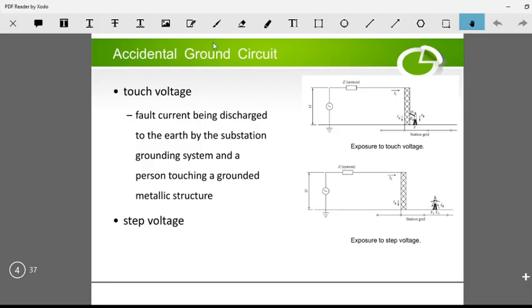So you have the touch voltage and the step voltage. Let's talk about touch voltage first. Touch voltage is defined using the fault current being discharged to earth by the substation grounding system, and a person touching a grounded metallic structure. If a person working in the substation touches this metallic structure, there could be a fault current flowing through the person to the ground. So you have the fault current, and some of it will go through the structure to the ground.